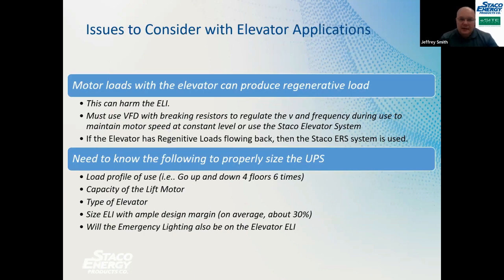Motor loads can harm the emergency lighting inverter. There's got to be a VFD with braking resistors in order to not require load banking - that's what's out there right now. With regenerative loads, we have to put in the Staco ERS system, which puts a load bank into the system to block out the regenerative power.